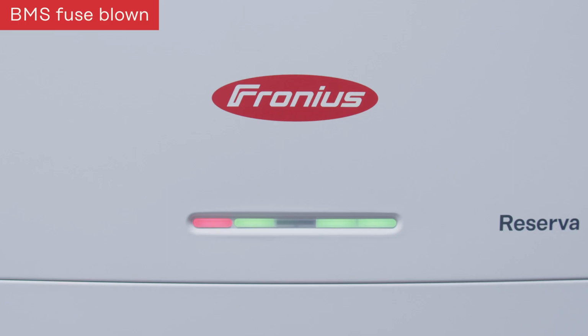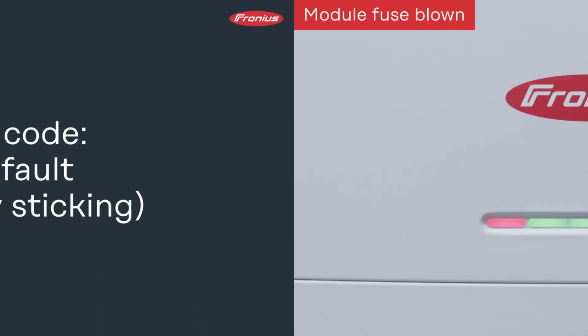Furthermore, there are failures like, for example, a blown fuse within the Fronius Reserva. The first such failure can be that the HV box fuse is blown, and with this LED status you can see that the internal fuse of the HV box is blown. Second failure can be that the fuse on module level is blown, so this would mean that on the module level the fuse is blown, and then you will see this LED status.